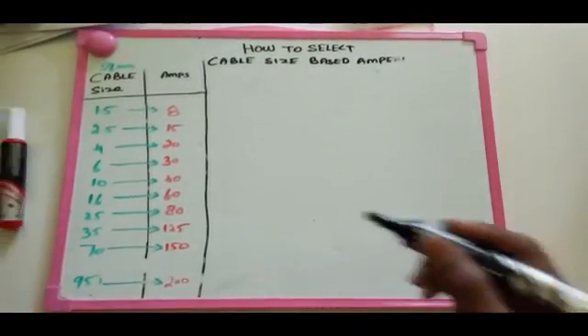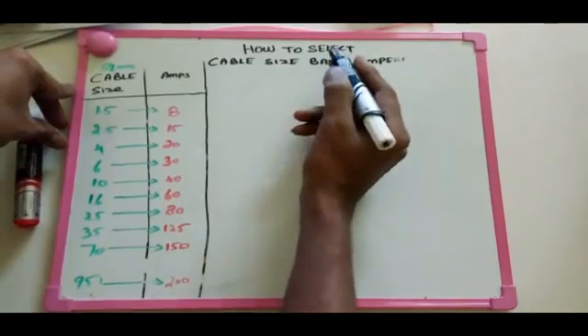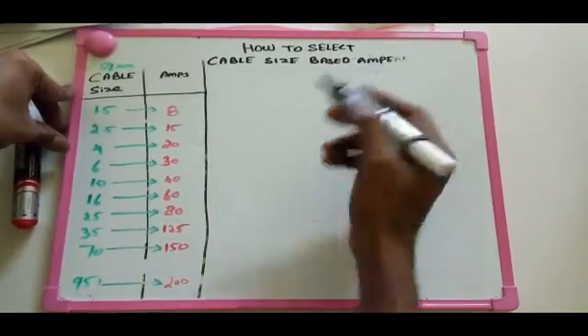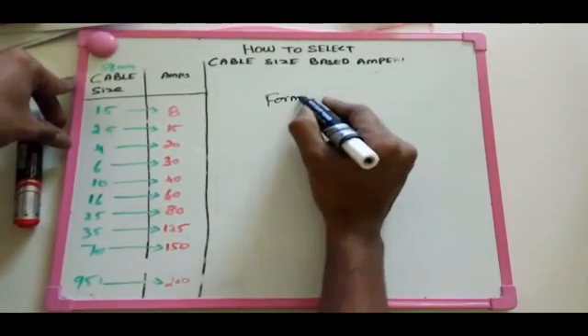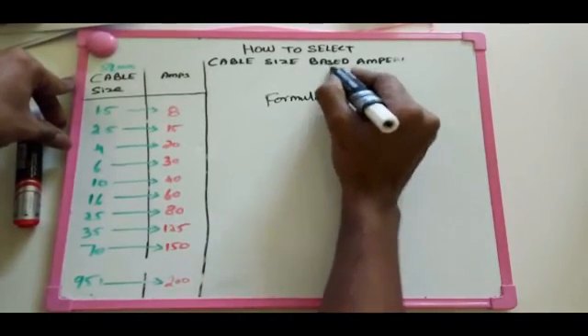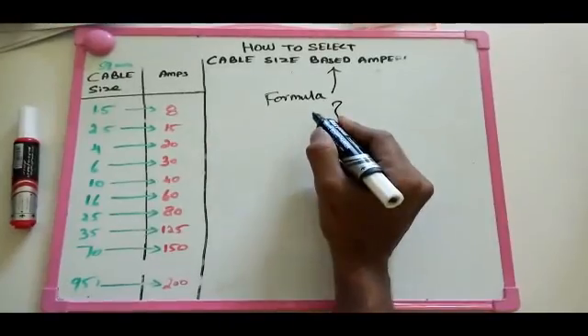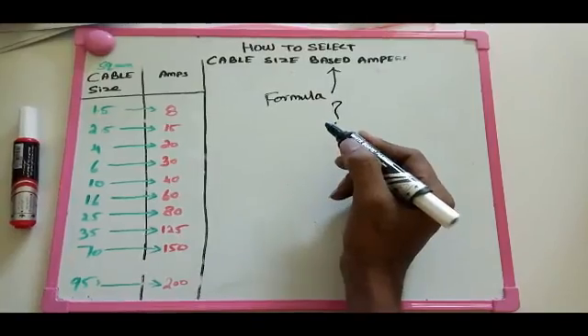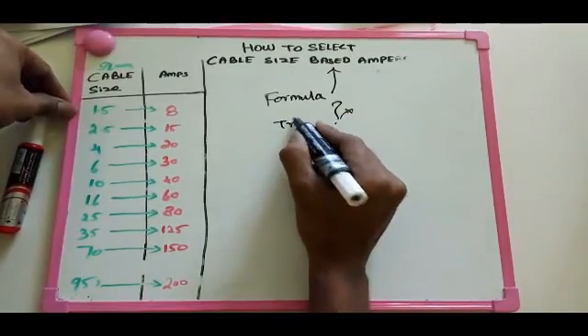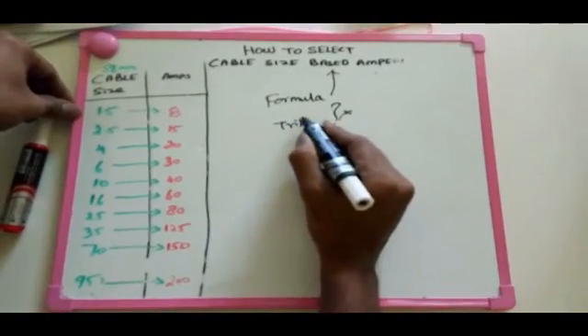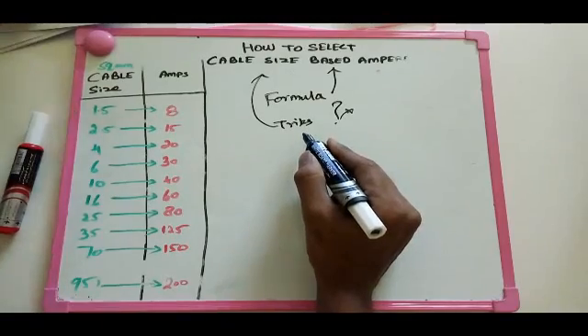Today we are going to see how to select cable size based on ampere. For the last month, many people have been asking for this — what is the formula for cable selection, how to do cable selection based on ampere rating. That's why I made this video. I don't have a strict formula, but I have some tricks to select cable directly without a table. If you have a small calculator, you can easily calculate this.